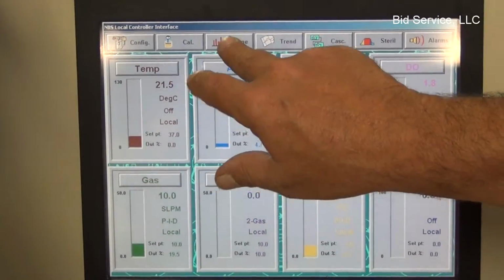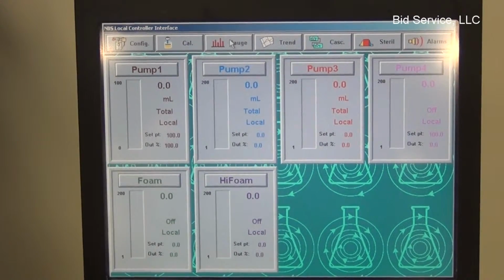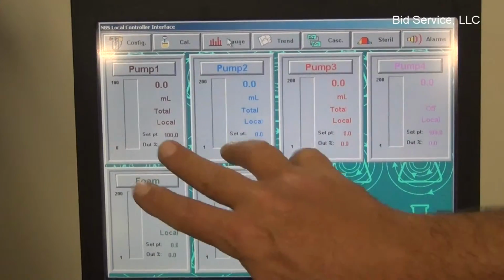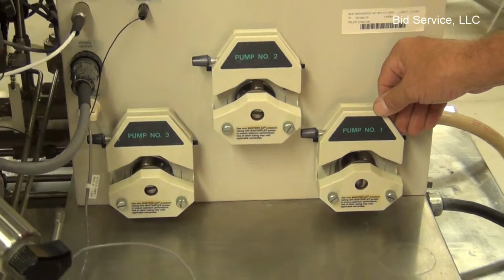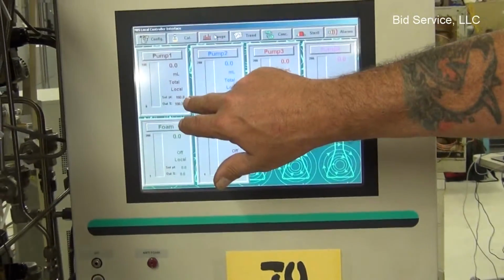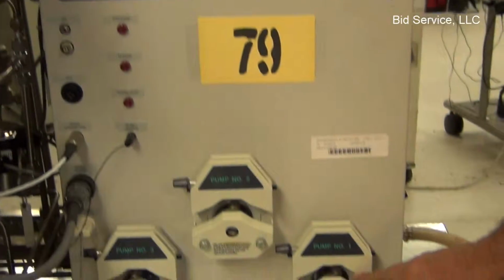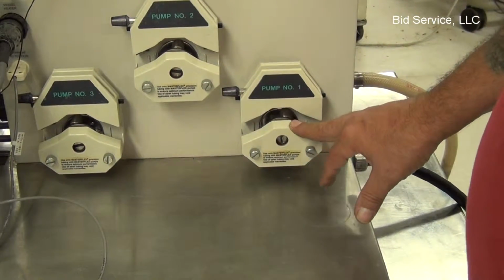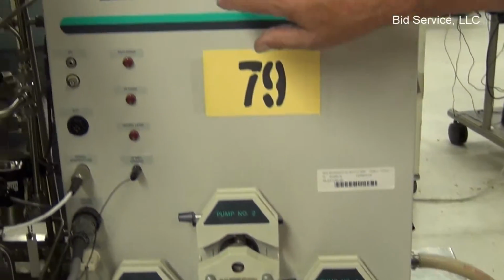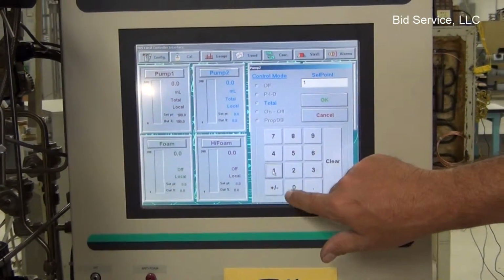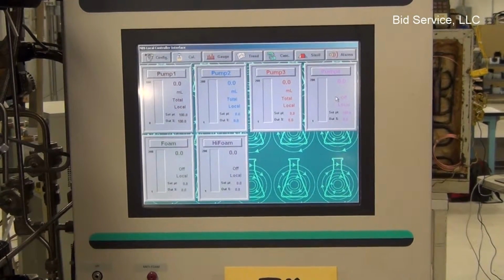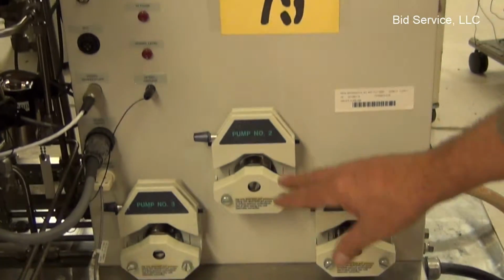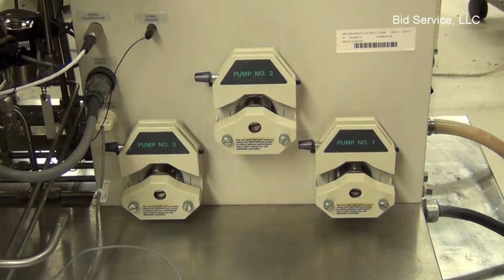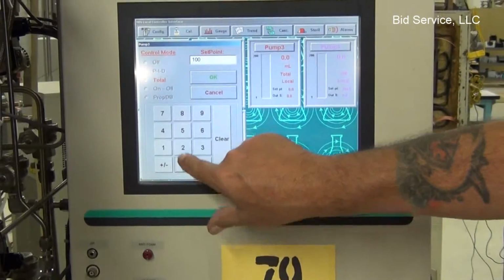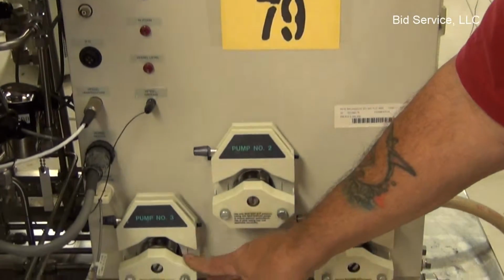And by hitting the gauge button up here, we flip to page 2. There's only 2 pages. And have your different pumps. These 3 pumps correspond to down here, and you can see they're numbered. Okay, and as you can see, I've got pump number 1 on right now, and you can see that pump number 1 is turning. So I'll go to pump number 2. This may take a few seconds to kick in. There you go. And now you can see pump number 2 is turning. I'll go to pump number 3. And you can see pump number 3 has started.